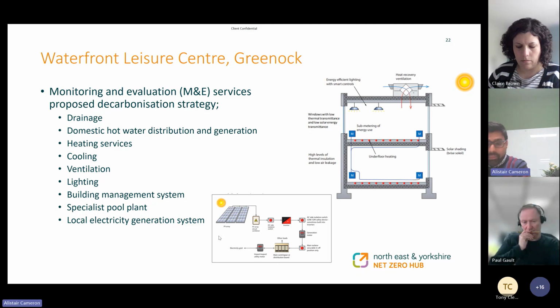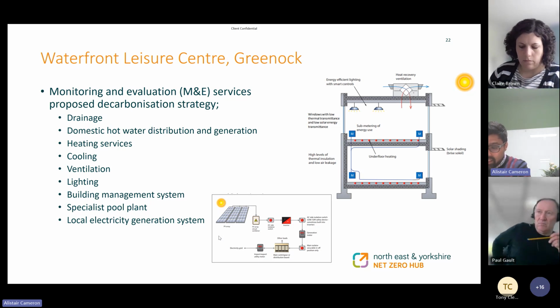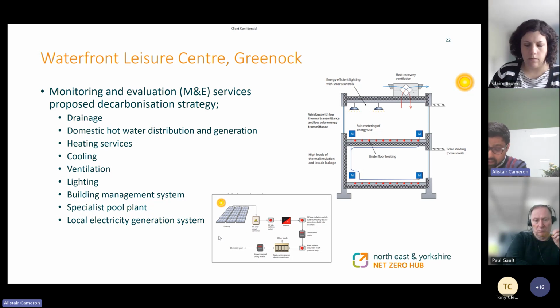Lighting, again, there's obvious benefits of upgrading the lighting to LED and providing sensors on that light to daylight. The building has lots of glazing, so there's opportunities there to link the lighting to the daylight levels. And also, because we have specialist pool plant, again, they're all 25 years old. So with modern advances in pool technology, we could upgrade the filters to ceramic membrane filtration, which would save water by around 50%. We can take advantage of more modern methods of chemical dosing, and upgrade the circulating pumps associated with the pool plant to more efficient pumps.